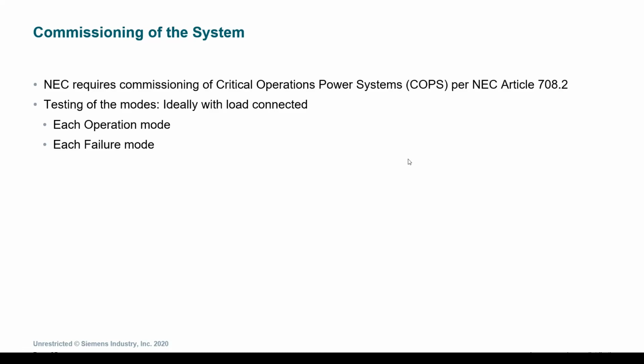When it is commissioned, it is tested in both an operation mode and a failure mode, and then also, as part of the facilities training, to train them to manual parallel the generators if something does not function the way it's supposed to in its automatic mode. One important part, as we discussed the arc flash settings and breaker coordination earlier, is just to review all of the circuit breaker settings to make sure that they are set to meet all of the arc energy reduction requirements and breaker coordination requirements.